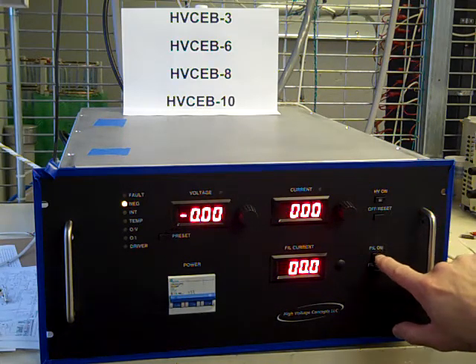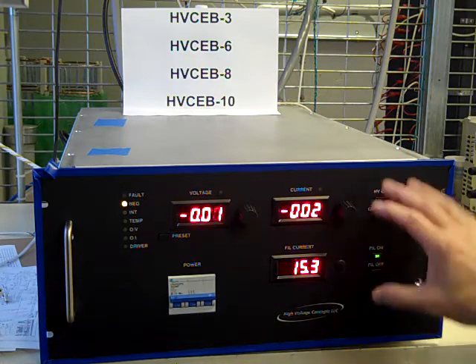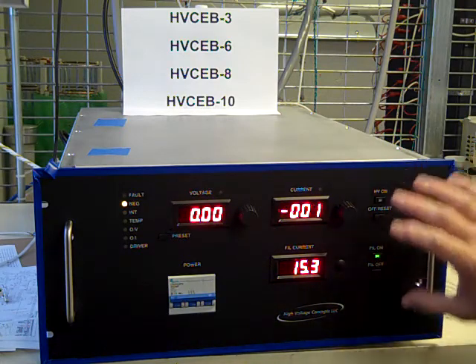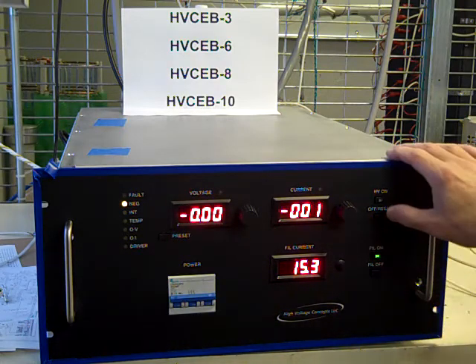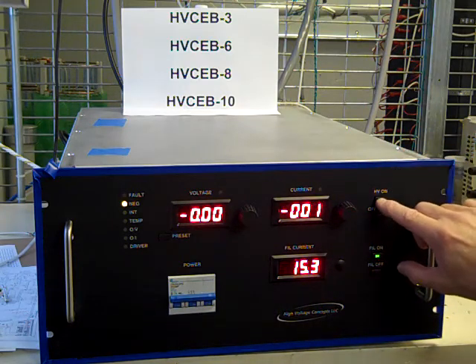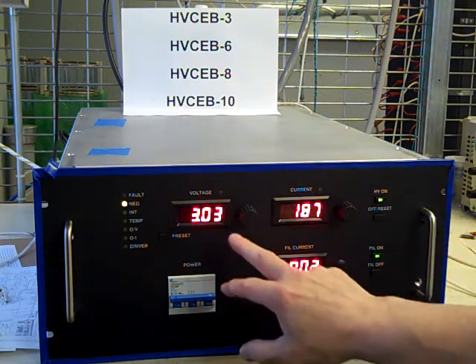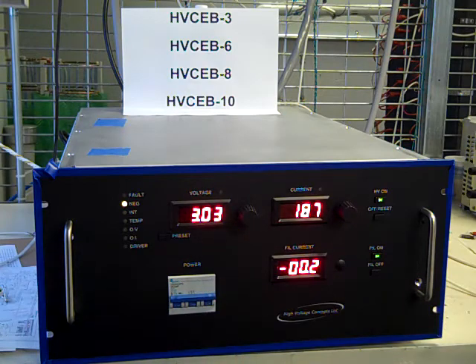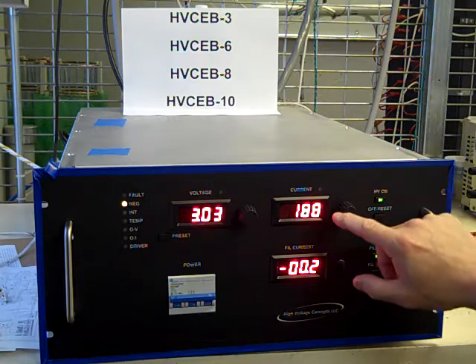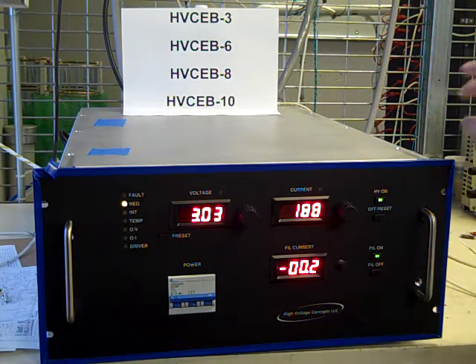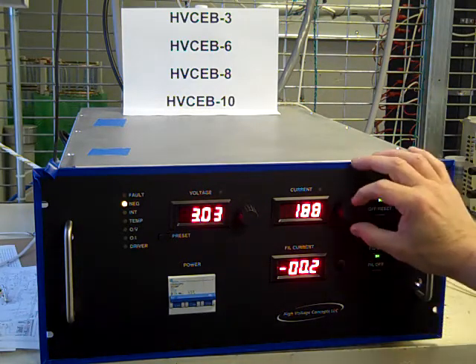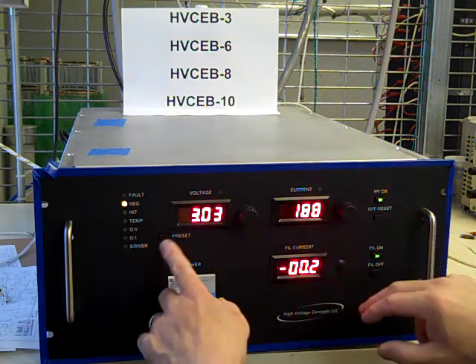Because we need to have the filament on first, so the power supply knows that you need to do this sequence. Once we turn high voltage on, the power supply will go to the assigned voltage, and the current output, we have a resistive load now. So right now we're below the current set point.